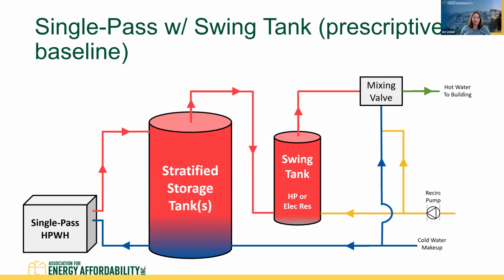The cold water makeup comes into the system and comes through the single pass heat pump water heater where it's heated up to upwards of 140 degrees typically. And then that hot water is delivered to the top of a large storage tank. With the single pass system, this is going to be a stratified storage tank. So if there's no draw on the system and the heat pump is running, that storage tank will get fully charged starting at the top down to the bottom over whatever the recovery time is based on the size of the system. So then you've got a fully charged tank.